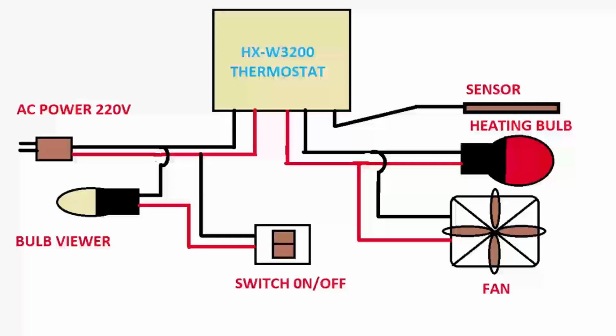the heating source. Here, I present to you in a simplified way the wiring circuit of the incubator using the thermostat HX-W3200. Here is the input part marked "entry" on the back of the device, black and red. This is the thermostat power supply, so as you can see in the diagram, we connect this part to the 220-volt mains current. There we have the output marked by the black and yellow wires. The name on the back of the thermostat is "output", so here it is a 220-volt output. You can see in the picture that the heating bulb and the fan are connected in parallel on this 220-volt output. The bulb used for viewing from inside the incubator connects to the 220-volt input.